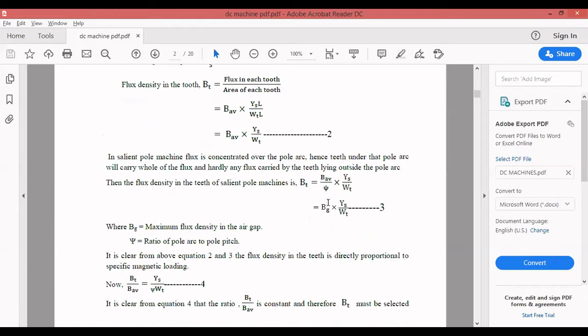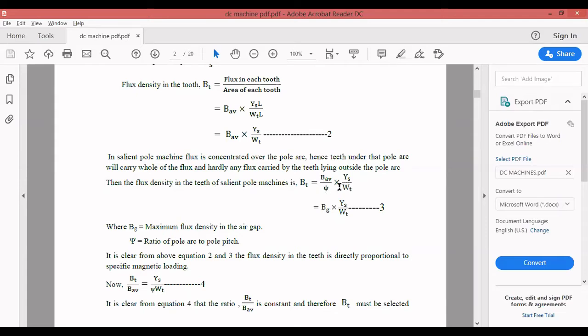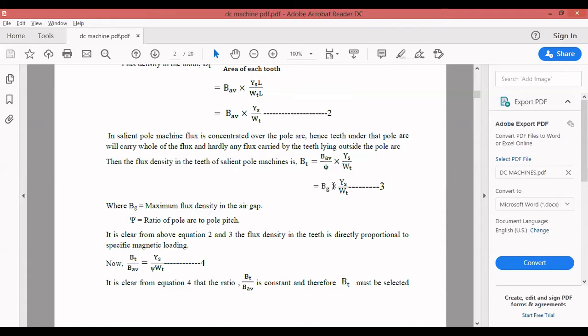Therefore, the flux density in the teeth of a salient pole machine is B_t = (B_av / psi) * (Y_s / W_t), where psi is the ratio of pole arc to pole pitch — equation 3. Here B_av / psi equals B_g, the maximum flux density in the air gap. Psi is the ratio of pole arc to pole pitch.